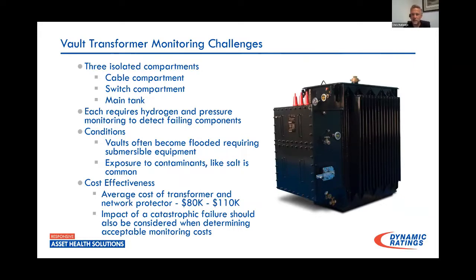Also, there are some other things that need to be considered when we're talking about maintenance, and something I took into consideration when designing monitoring for these vaults. They flood a lot, and even in Memphis, we're definitely not a coastal area such as New York, where they really struggle with this. But we would have water mains burst in the winter. We would find these transformers underwater, as much as 15 feet underwater at times. Sump pumps get clogged up in the vaults. You do have all your water mains running there.